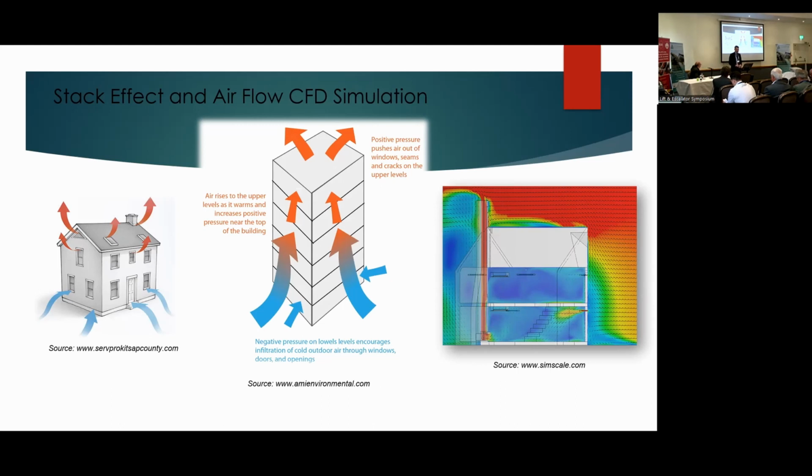As illustrated in the figures, the movement of air inside the shaft, or, as in the last case of the figure, the chimney of the building, is due to air temperature differences. Obviously, hot air rises. While it rises, it creates negative pressure, or a variation of the pressure in relation to the neutral pressure inside the shaft, which causes the spread of fire.